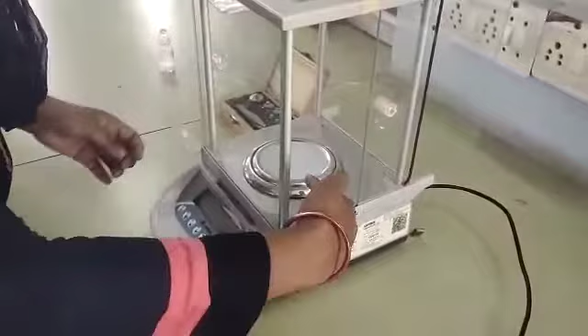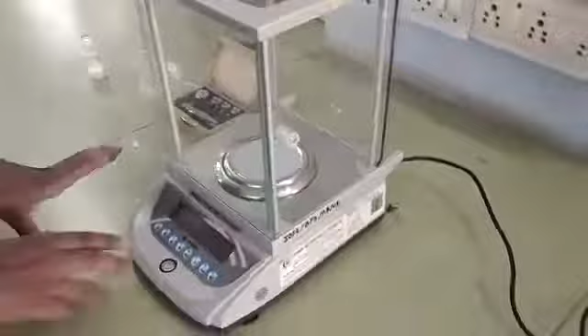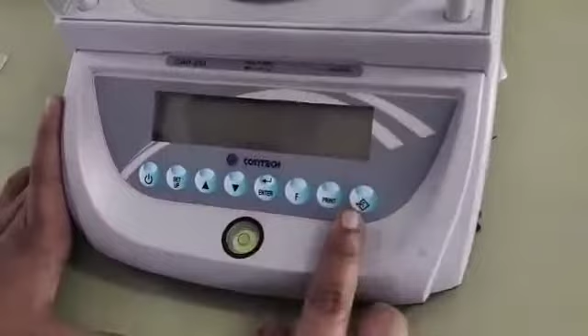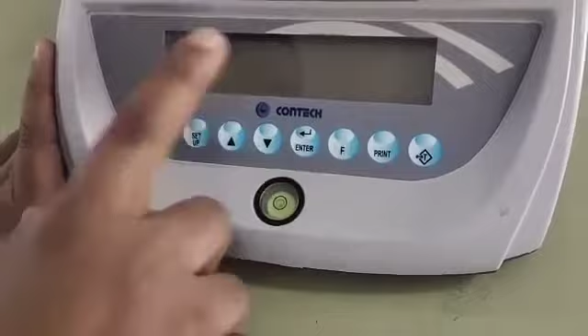Now let us become familiar with its parts. This is the glass enclosure for opening and closing the door. This is the circular pan where we load our sample. This is the control panel. You can see many keys are available here. This is the tare key to tare or zero the balance. This is the on or off key to turn the balance display on or off. This is the setup key for setting various parameters. There are 25 parameters available in this machine.